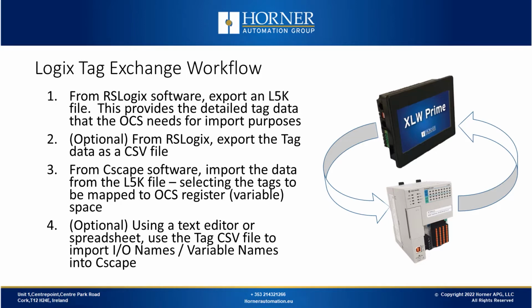Now let's talk about the workflow to get everything set up. We start out in the RS Logix software where you create the L5K file. In your project in RS Logix, you save as an ACD file, but then you do a save as to create the L5K file. Then there's an optional second step within RS Logix that we recommend, and that is to perform an export function of your tags as a CSV file. That's available in the Tools section in RS Logix.